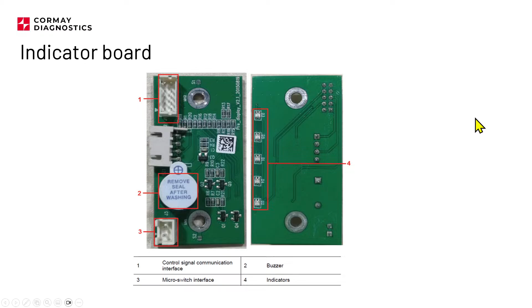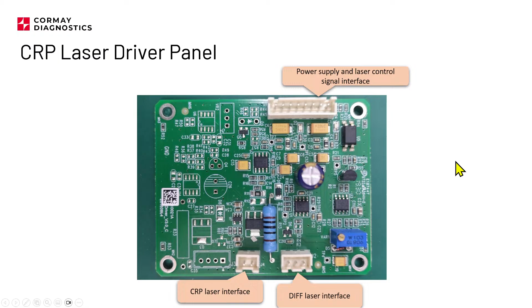Indicator board. So this is located on the front panel of the analyzer, and there is a buzzer and also a few LEDs, and those LEDs can change color according to the status of the instrument. CRP laser driver panel. So this is nothing special. It's just supplying constant current, constant voltage, I believe, to the laser unit, and just controlling the parameters of the power which is going to the laser unit.